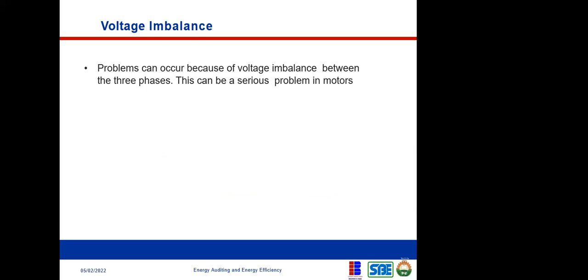So let me talk about voltage now. I'm going to talk about voltage with respect to imbalances in the voltages. When I talk about voltage imbalance, this is only applicable to three-phase systems. So you have three phases, the red, the yellow, and the blue lines. If the voltages across these three phases are not balanced, and remember that these three phases can be going into one single piece of equipment, then the voltage imbalance creates problems for this equipment.